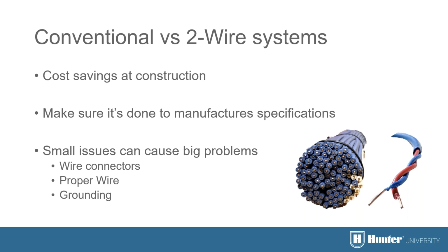We really try to stress this to our people when they take over a system. If it's two-wire, you need to go through it with a fine-tooth comb. Make sure you have the right wire connectors, the proper wire, and the proper grounding. Because if you don't have those in place, those issues may not come up until 6 to 12 months after you've been on the project. It's really difficult to go back to the customer and have that conversation: grounding wasn't used, and now we have mass numbers of decoders failing. I can replace those decoders today, come back next week and have 2 or 3 more bad if I don't have grounding in place. So it's really important that it be installed per specification.